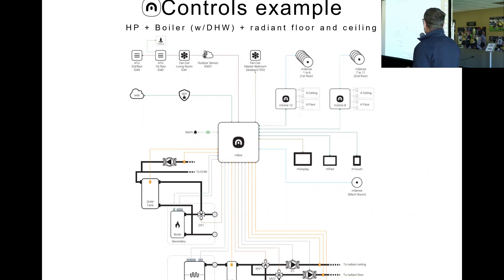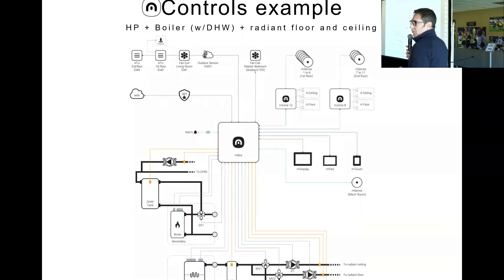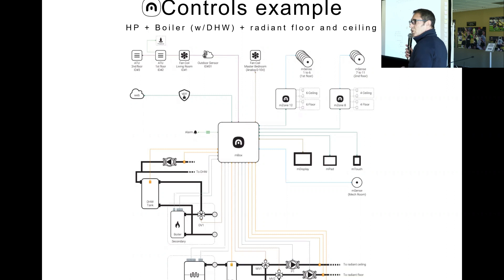On this side there is a Modbus line that will connect what we call the ATU — air treatment units. This project is for a house with two floors and 11 zones with both radiant ceiling and radiant floors. We put one unit per floor, so two different air treatment units. We also added a fan coil in the master bedroom controlled with 0-10 volt analog output to modulate fan speed based on how far we are from the dew point, and there is also a fan coil in the living room.